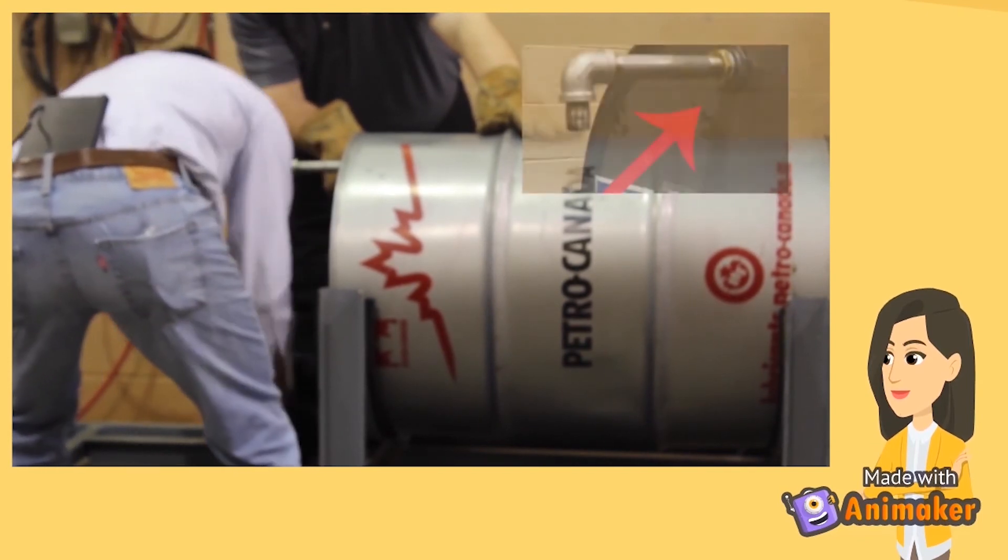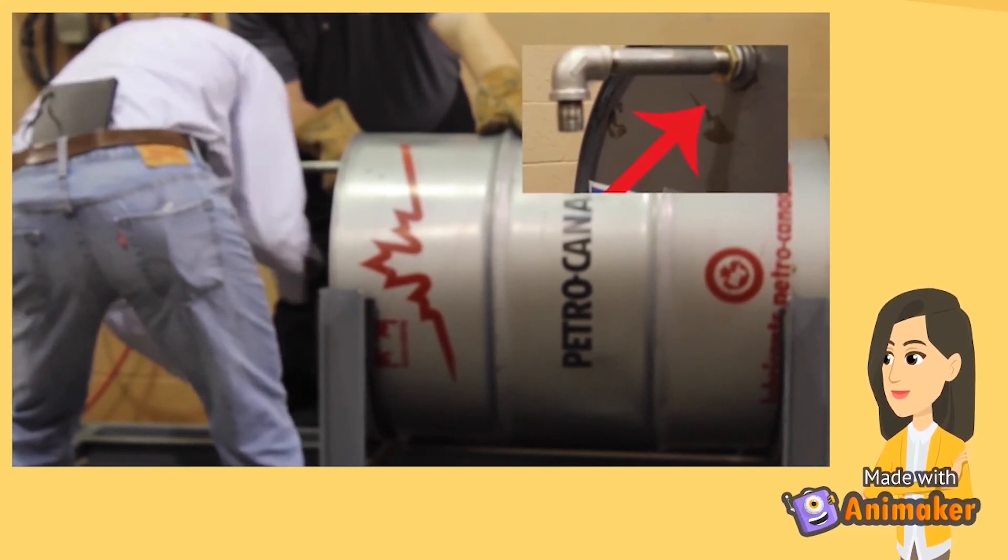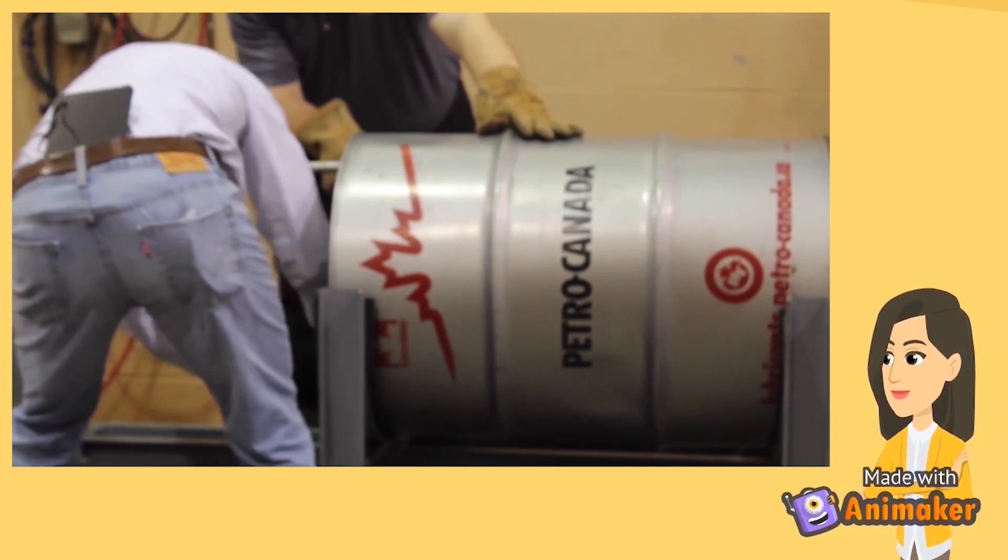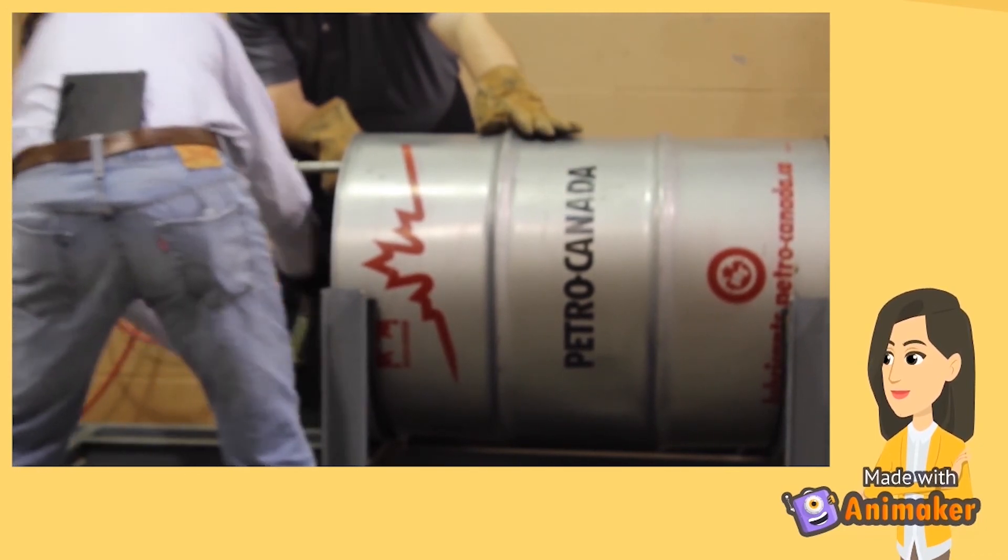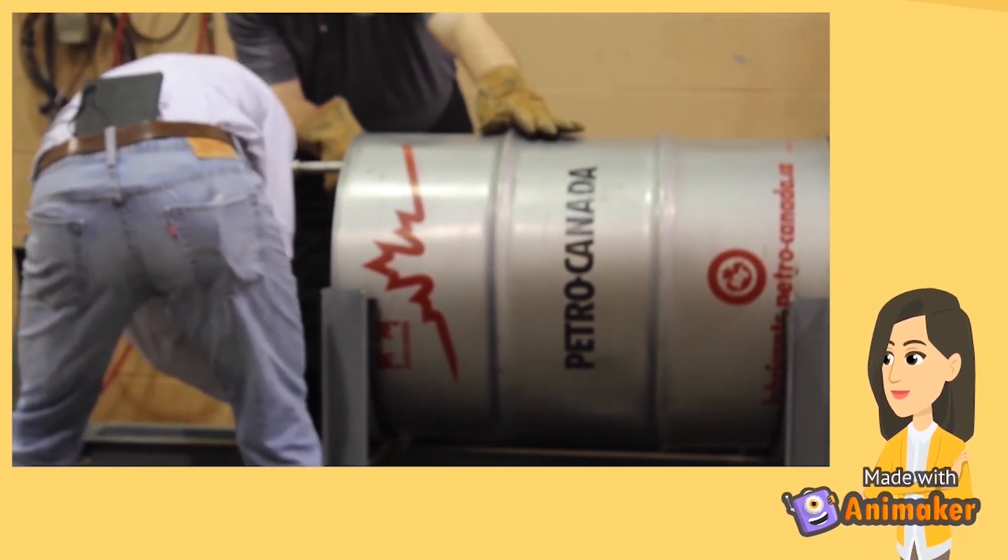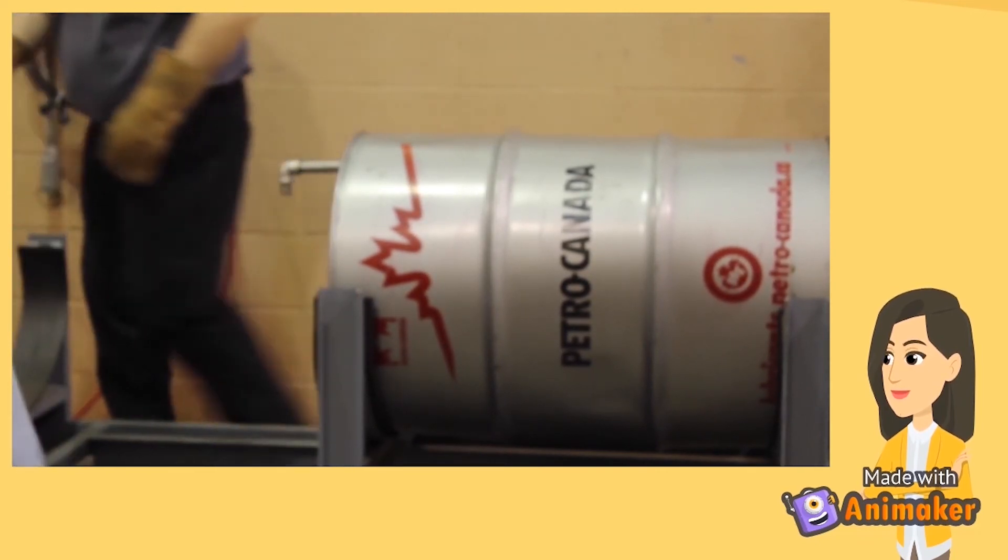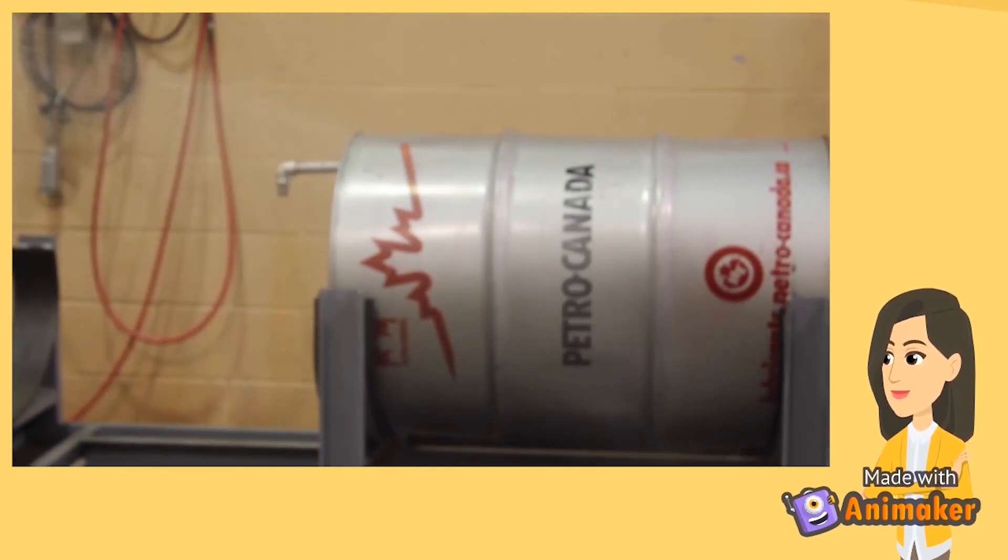This barrel has a three-quarter inch vacuum breaker installed in the smaller bung opening. Once the vacuum inside of the barrel reaches one inch of mercury, the vacuum breaker opens allowing air to replace the collapsing steam and thus preventing the barrel from collapsing.